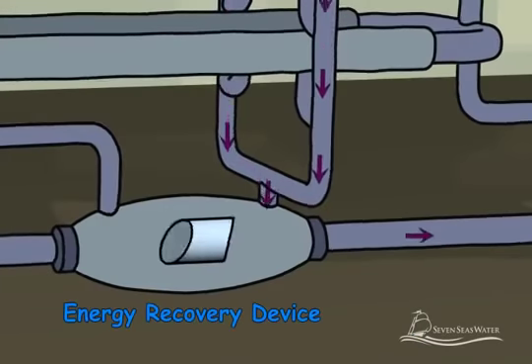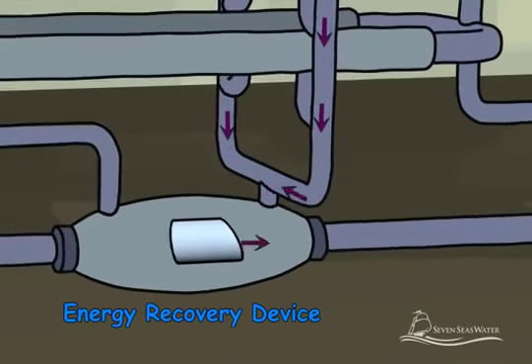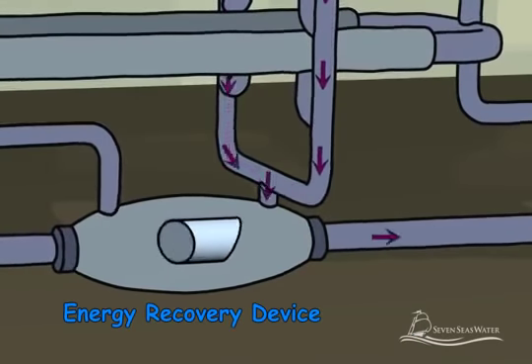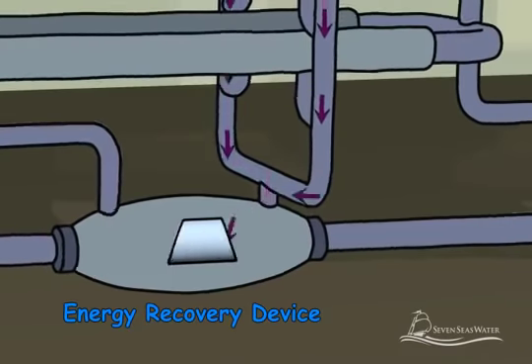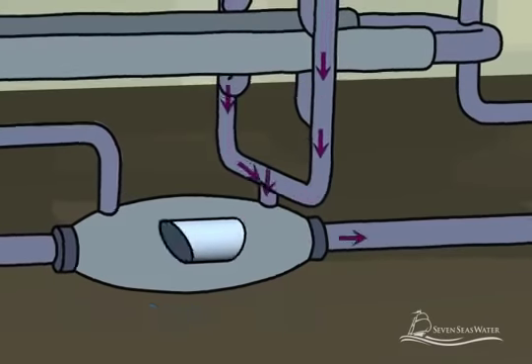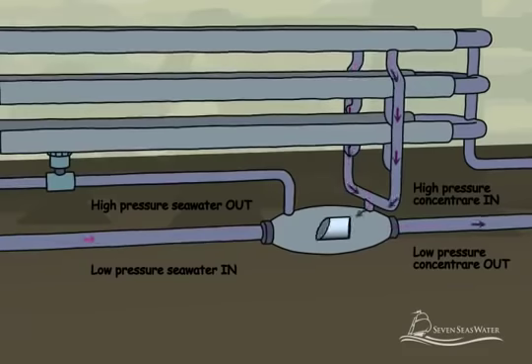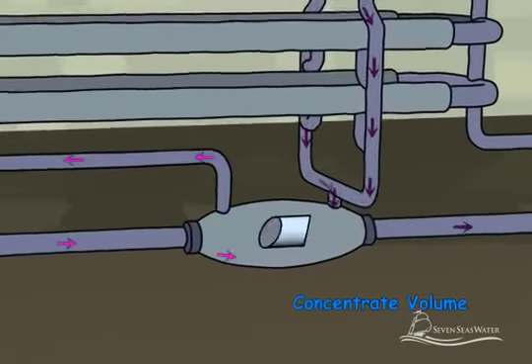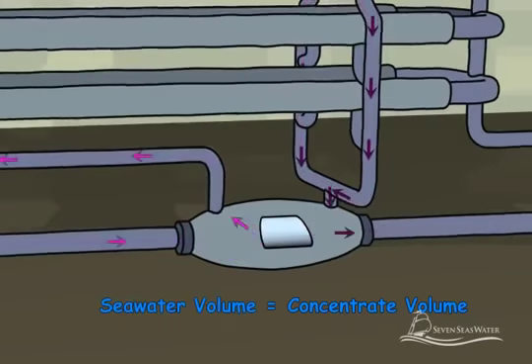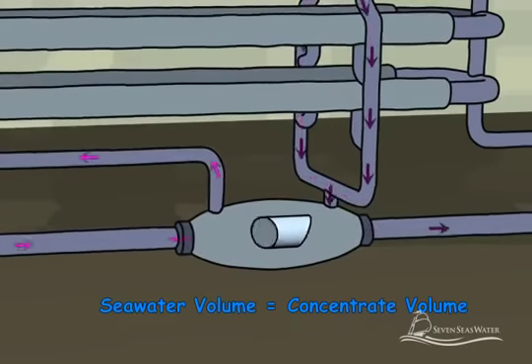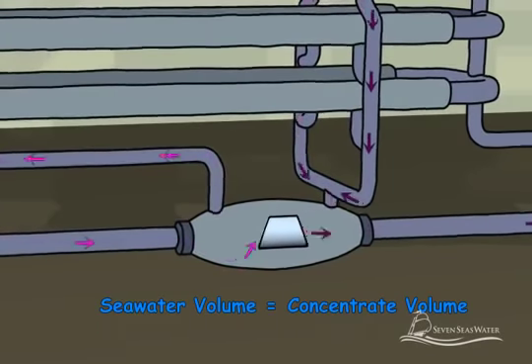To reduce the energy that is required to operate the reverse osmosis plant, the pressurized concentrated stream is piped into an energy recovery device. Here, up to 98% of the energy of the concentrated salt stream is transferred to an equal volume of the incoming seawater in an isobaric energy recovery device.